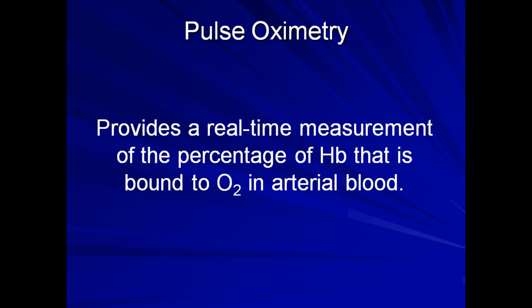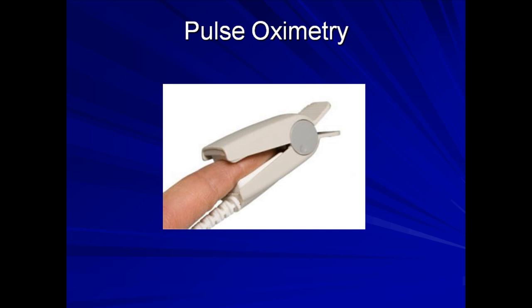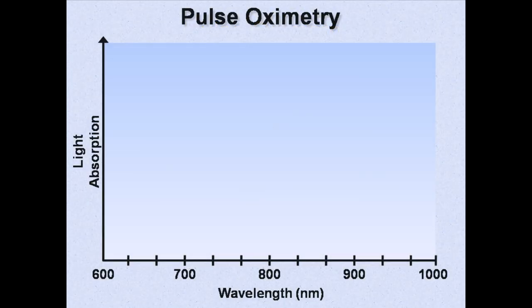We'll now move on to pulse oximetry. Pulse oximetry provides a real-time measurement of the percentage of hemoglobin that is bound to oxygen in arterial blood. Here's a picture of a typical pulse oximeter probe — usually a small hinged device that loosely clamps around the fingertip. There are also probes that are thinner and taped directly to the patient's skin for less artifact. To understand how this device works, we need to look at a chart relating the relative degree of light absorption of oxygenated and deoxygenated hemoglobin over a range of wavelengths.